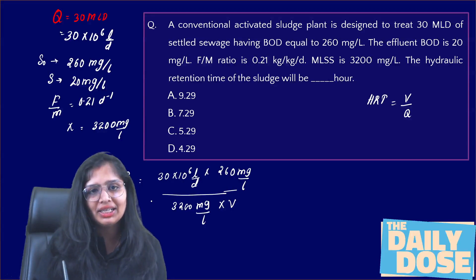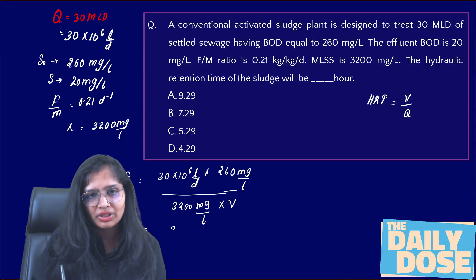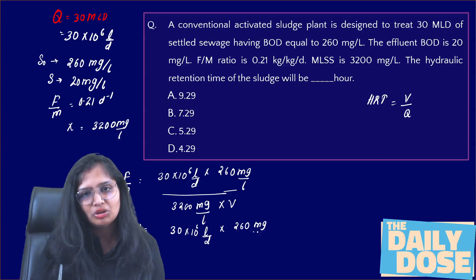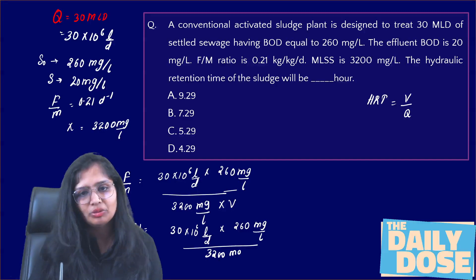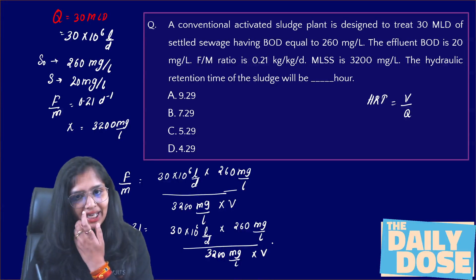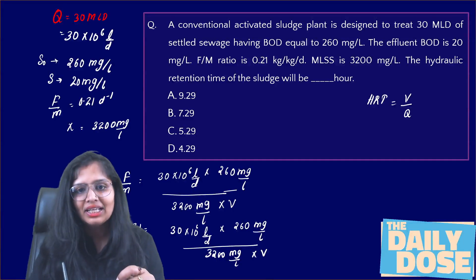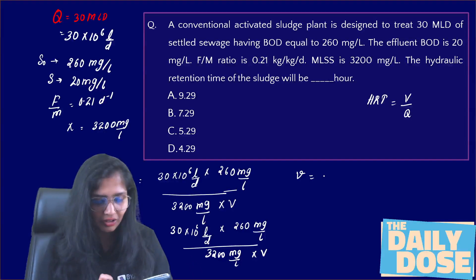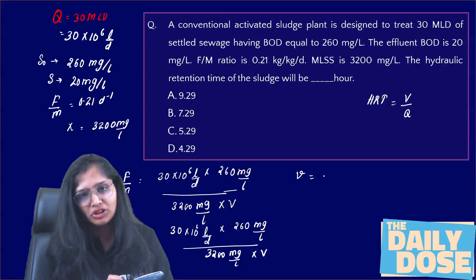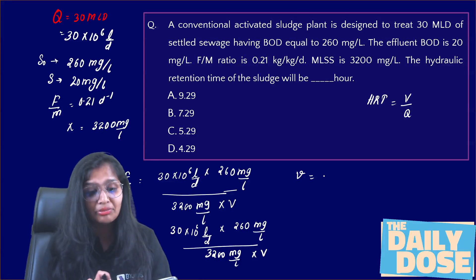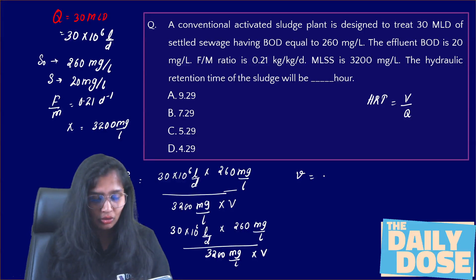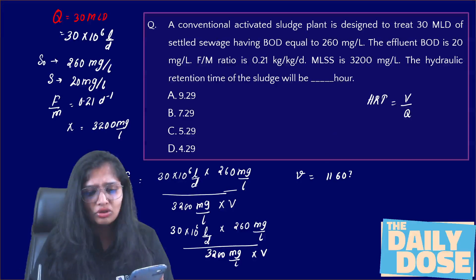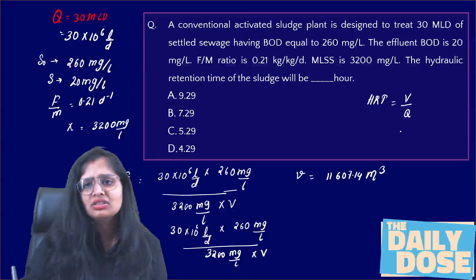The F/M ratio is 0.21, so: 30 × 10⁶ L/day × 260 mg/L divided by (3200 mg/L × Volume) equals 0.21. The mg/L units cancel out, leaving volume in litres. Converting to cubic metres by dividing by 1000, the volume comes out to 11,607.14 m³.